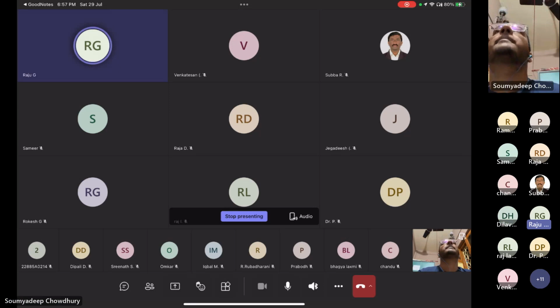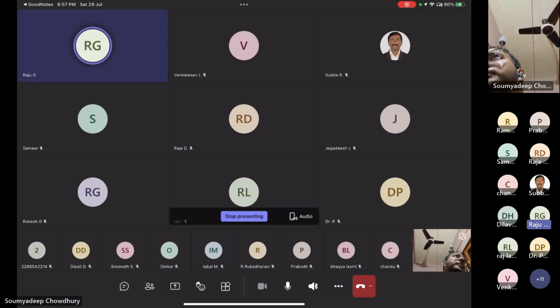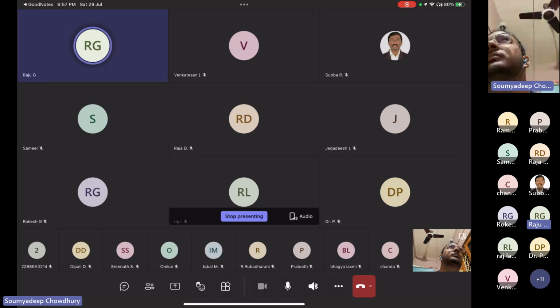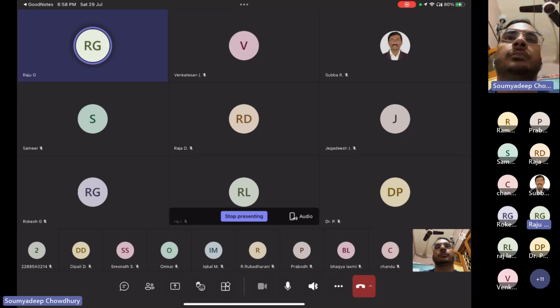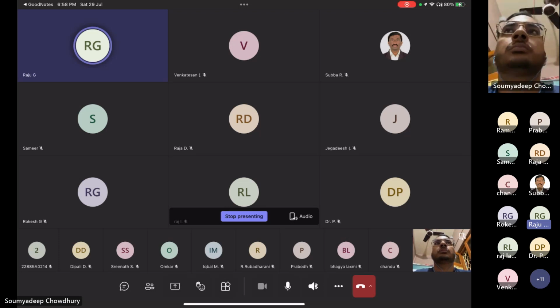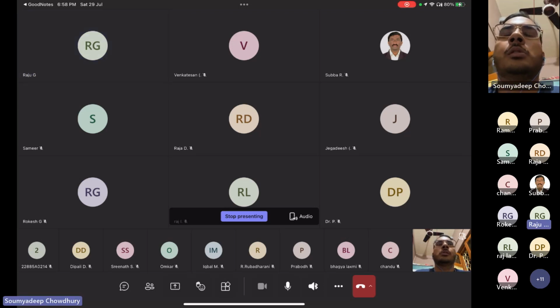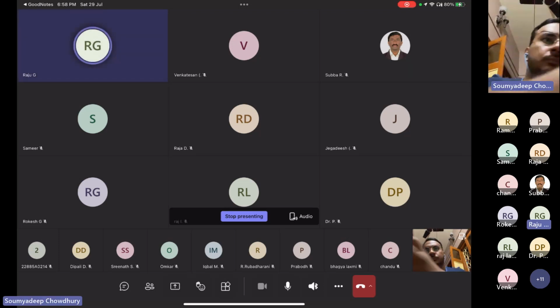When the system voltage is very high, the capacitance will be dominating more than the inductance. Therefore, the characteristic impedance, the impedance behind this, it should be varying. It cannot be 250 ohms. For low voltage it will be maybe more, for higher voltages it will be less, because of the capacitance dominating, especially in ultra high voltage systems, and inductance will be less compared to the capacitance.